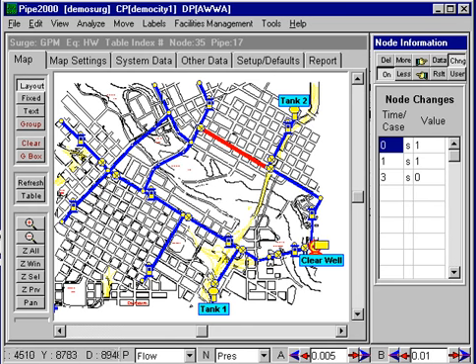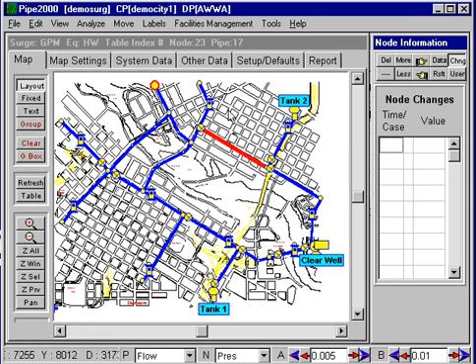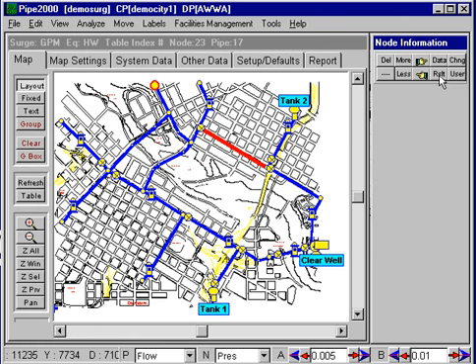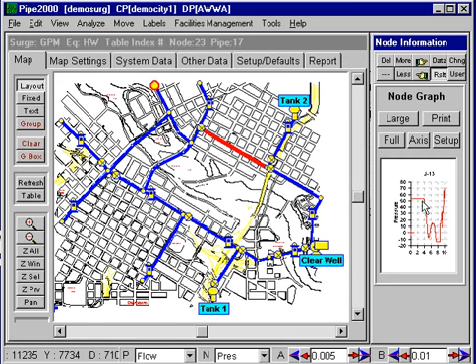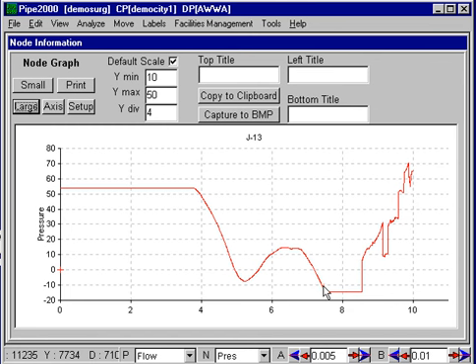For example, we can look at the pressure at any of the individual nodes. I'll select this particular node out in the system, turn on the results, and see the pressure out there. Looking at it in full screen, we see that the pressure has dropped — it took about three or four seconds for the transient to be felt there. It drops down and actually goes down to a bottoming out, which is cavitation, and that's usually not very good. You can get intrusion of bad water, and there are a lot of things that can happen. If we run this long enough it will eventually steady out at the new pressure, which is just slightly below the original pressure — it may be around 50 psi.